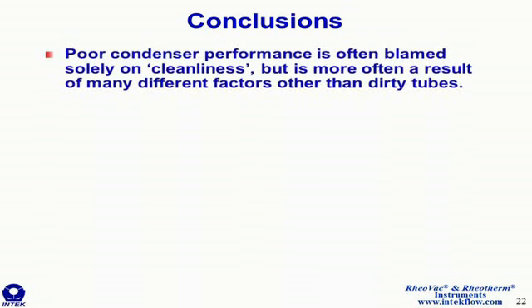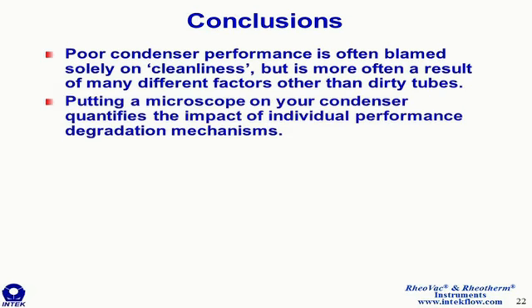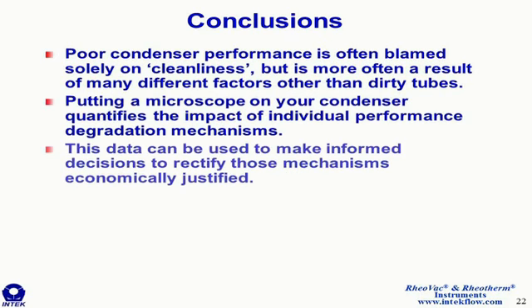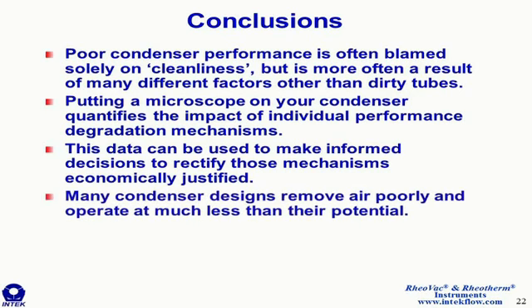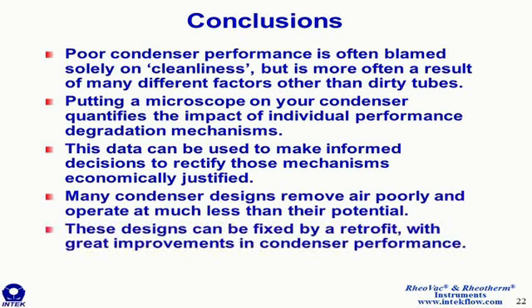So here are some conclusions. Poor condenser performance is often blamed solely on cleanliness, but it is more often a result of many different factors other than dirty tubes. Putting a microscope on your condenser quantifies the impact of individual performance degradation mechanisms, and with that data, you can make informed decisions and correct only those mechanisms that are economically justifiable. Many condenser designs remove air poorly and operate at much less than their potential, and these designs can be fixed by a retrofit with great improvement in condenser performance.